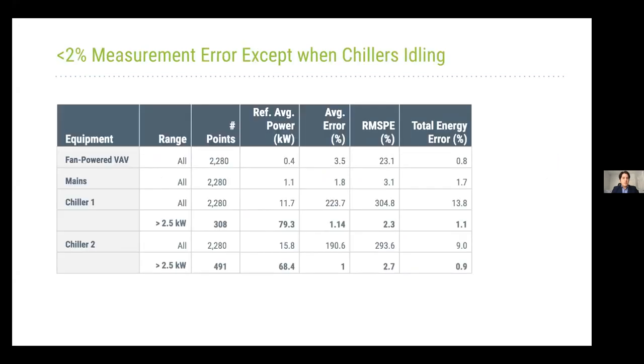I'll be summarizing what the results were for this. So I think a great takeaway is the title in this slide. We found high accuracy for this technology, except whenever the chillers were idling. And as I mentioned before, we found the delta configuration to be the culprit here. But I just want to show you in this slide that even once we pass that threshold, even the chillers perform really well at below 2% for the total energy error. So I think that's a great takeaway here. We found that the technology can definitely produce this type of results. It's reliable, and these results can be replicated as well. We can go to the next slide, please.